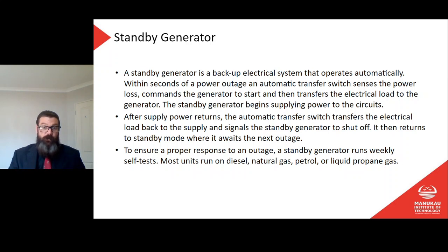When the main supply turns off, the contactor for the generator supply turns on, and the contactor for the main supply turns off. When main supply comes back on, it automatically opens the contactor for the generator supply and closes the contactor for the main supply. So that's how that would work. You might have a changeover contactor, but let's say two contactors just to keep it simpler. This is not part of the test. I just think it's interesting and important to understand how that works. You'll have another little circuit that goes to the generator and does things like automatically turn it off, switch the load over, all of that kind of stuff. But usually it's just a changeover contactor system that turns one off, one on.